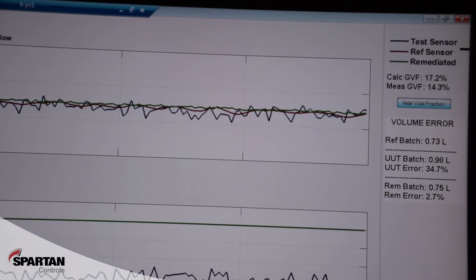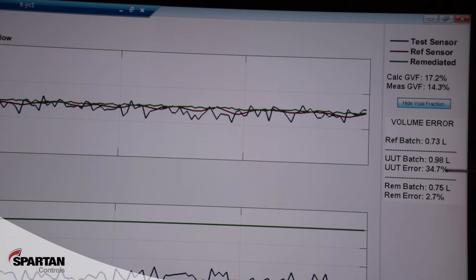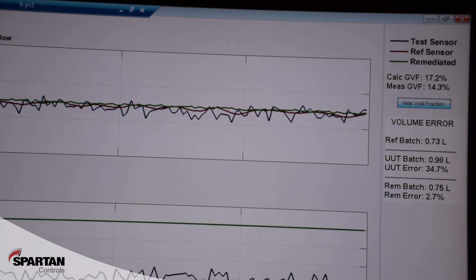Once our test is complete, we can look at what we calculated and what we actually measured using the advanced phase measurement algorithm for gas void fraction. In this case, just a little bit under 15%. But what's more important is my unit under test, or my test meter, had a 34.7% error from the reference meter in the volumetric measurement.